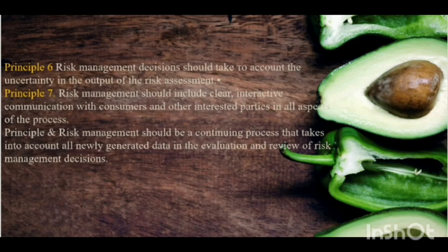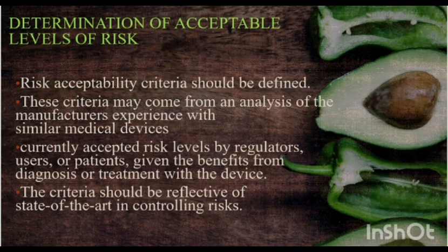Then when we move on to the risk assessment, we move on to the 4 main important criteria of risk management. The first one is the determination of acceptable levels of risk. So here the risk acceptability criteria should be defined, and at the same time these criteria should come from the analysis of the manufacturer's experience with similar medical devices.